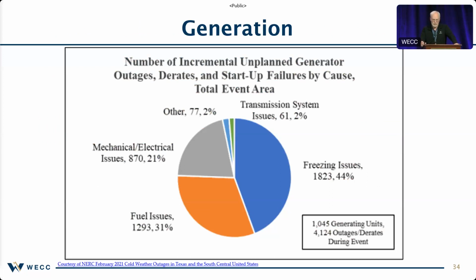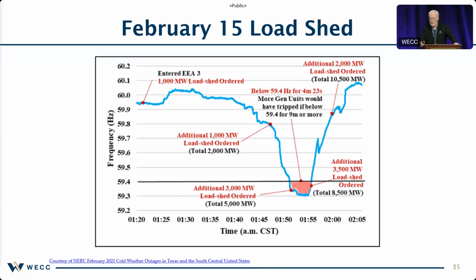So 1,045 generating units ended up having 4,124 different outages. So a generating unit went out, came back into service, tripped out again, which is why there are more outages than there were units that were impacted. Many of these were wind generation. Obviously, there was a lot of thermal generation also. So we're looking at a snapshot here of the frequency in the ERCOT interconnection over a 45-minute period. So we can see we start out there at 1:20 in the morning. We're about 59.9 hertz going into the system.